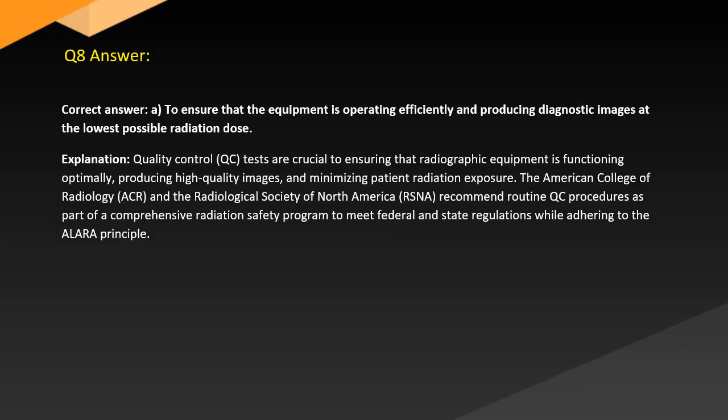Answer. Correct answer. A. To ensure that the equipment is operating efficiently and producing diagnostic images at the lowest possible radiation dose. Explanation. Quality control, QC, tests are crucial to ensuring that radiographic equipment is functioning optimally, producing high-quality images and minimizing patient radiation exposure. The American College of Radiology (ACR) and the Radiological Society of North America (RSNA) recommend routine QC procedures as part of a comprehensive radiation safety program to meet federal and state regulations while adhering to the ALARA principle.